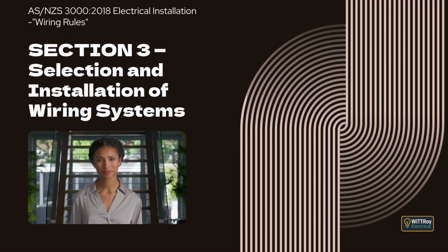Clause 3.9.4.4 Protection methods. This clause explains that protection may be achieved by providing adequate mechanical protection, by using earthed metallic protection capable of operating a short-circuit protective device under fault conditions, or by protection using an RCD with a maximum rated residual current of 30 mA. Additional notes clarify how these methods apply to different wiring systems. Clause 3.9.5 Wiring systems installed vertically. This clause explains that vertically installed wiring systems must be arranged to avoid damage caused by their own weight. Adequate support must be provided, with support spaced to prevent strain, typically not exceeding 8 meters unless otherwise recommended by the manufacturer.